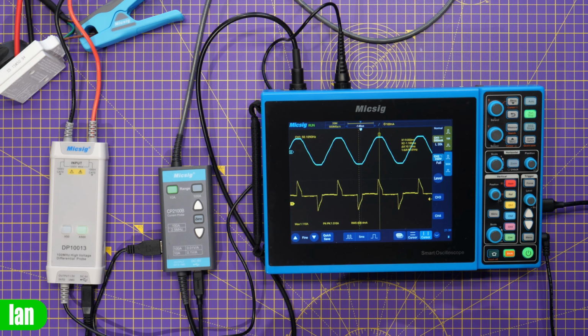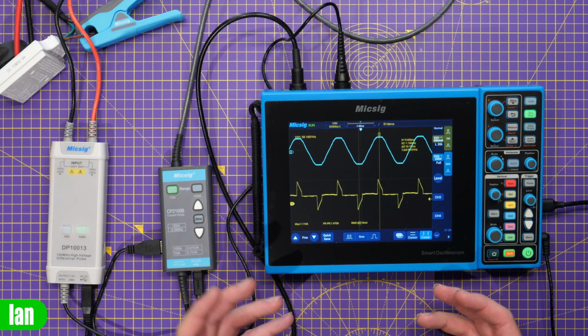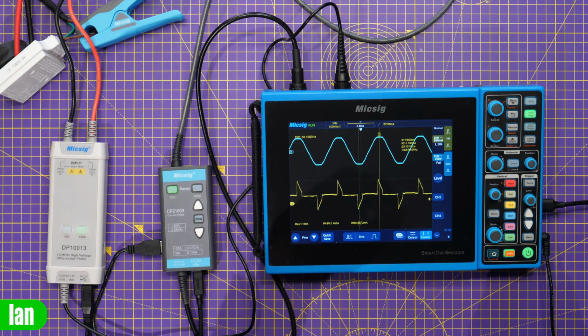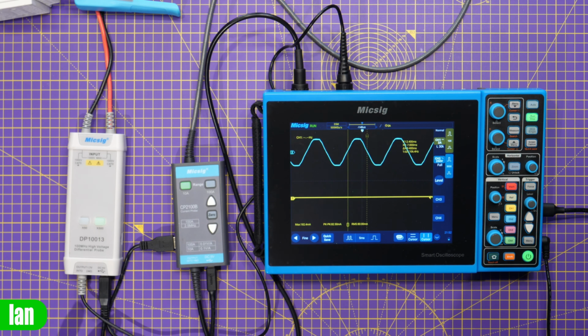However, if we move over to a different kind of load, something such as an inductive load, for instance, that will start to change how that curve looks. So what I will do is go and swap that over, and we'll come back and take a look at that. Okay, so we've got an inductive load connected up, and this is a small bench grinder. It's not a very large motor on this, but it is enough for me to be able to demonstrate the effect.